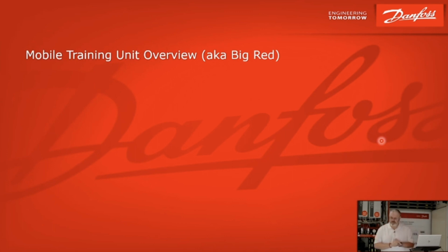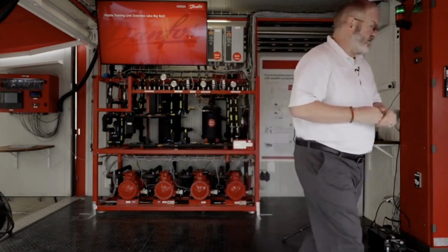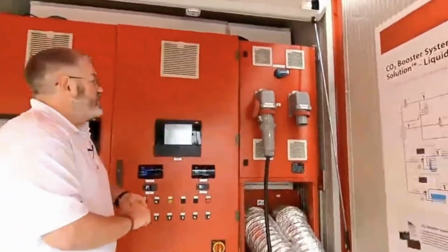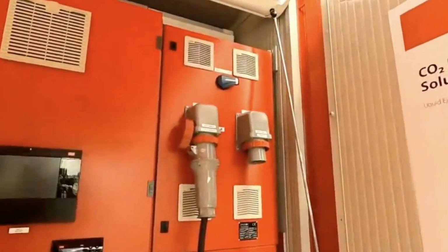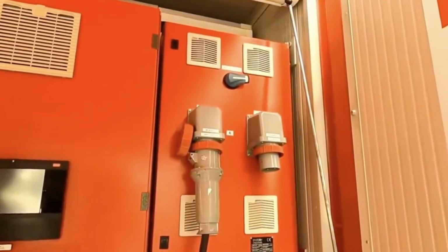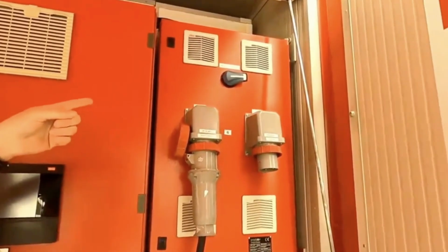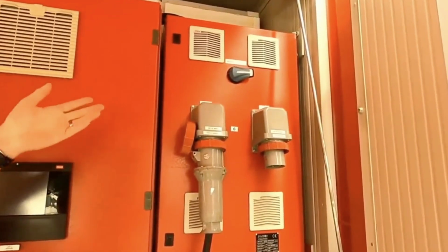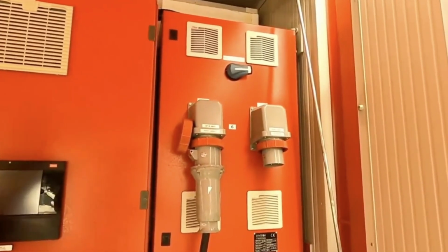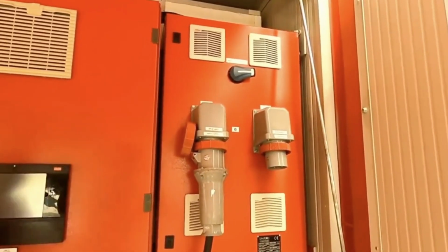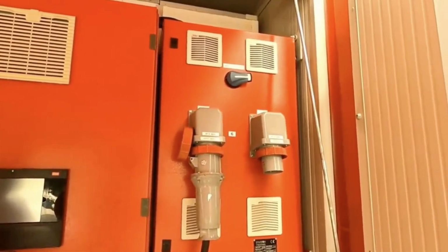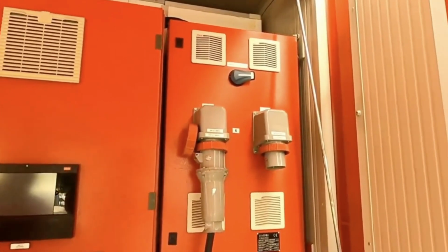So the unit itself, it's a medium temp CO2 transcritical system. We call it affectionately within Danfoss Big Red. If I can get a close up here, we're going to go over here. As far as the construction of the unit, it's used all around the world. So we've got a buck and boost transformer that lets us use either 460 volt for the US and North America, and then we can switch it over to 400 volt for South America and the rest of the world that uses 380.